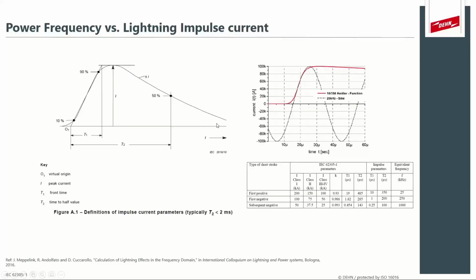That means the lightning impulse is positively charged, and this wave shape by IEC is characterized as a 10/350, or 10 by 350 microsecond wave shape. So this 10 by 350 wave shape is denoted by these parameters on the input. The first value, 10, describes T1, which is the rise time to its peak value. So for example, in the first positive stroke, if we talk about T1 being 10 microseconds, it means that the impulse will have a rise time up to its peak value in 10 microseconds. T2, or the second value, 350 microseconds, describes that the wave shape will decay to 50% of its peak value over 350 microseconds.